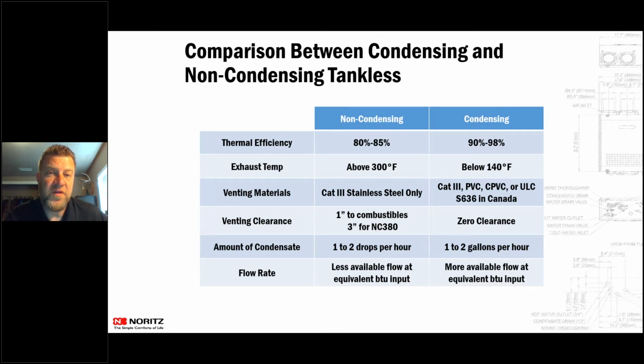The elevation, we have settings in the unit that offset the elevation side of it, so it knows what elevation it's at, so it can still keep up with the exact flow rates that we have set for all of those units. Just to give you an example, a unit that's 199,000 BTUs, like our EZ111 unit, it's 11.1 gallons per minute is what we say that unit is, but that 11.1 gallons per minute is at a 35-degree rise. In our books, we actually have a flow rate chart. So in Park City, if you had an EZ111 that's 199,000 BTUs, we always size off of winter temperature. So we would look at like a 70-degree rise instead of a 35-degree rise there, which would be like 5.9 gallons per minute going through that unit.